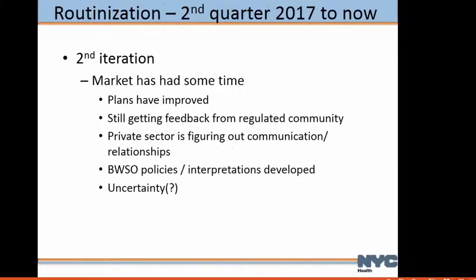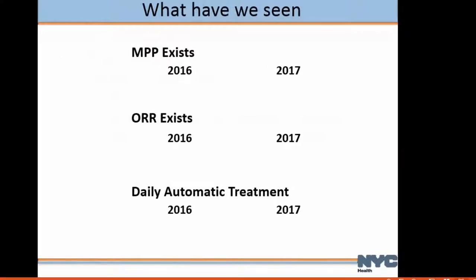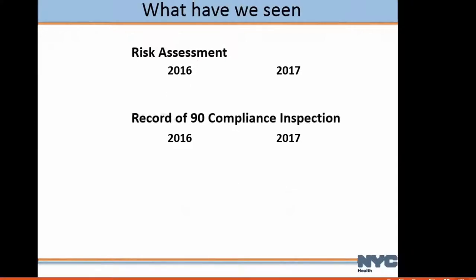In the second iteration, the market has had some time and plans have improved. We're still getting feedback from the regulated community, and it's getting better. In 2016, major violations included: did the plan exist, did records exist, did systems have daily automatic treatment — they're not required to have it but it does make things easier. And here's what we see now — lots of improvement. Same thing with the risk assessment: did they have a risk assessment with the proper elements, and do they have a record of all four of the previous 90-day compliance inspections? There's improvement there too, though the compliance inspection number is probably a little low because we're looking back at all four quarters and those first quarters would have been missing.